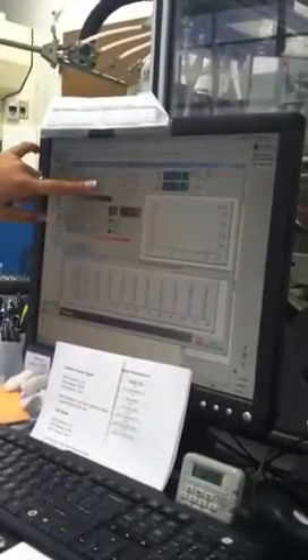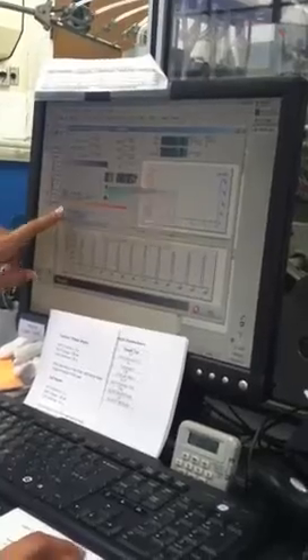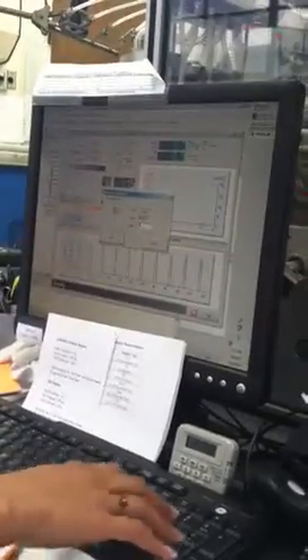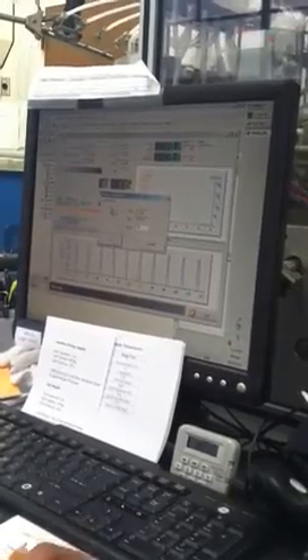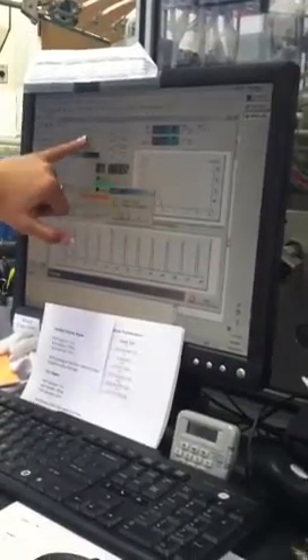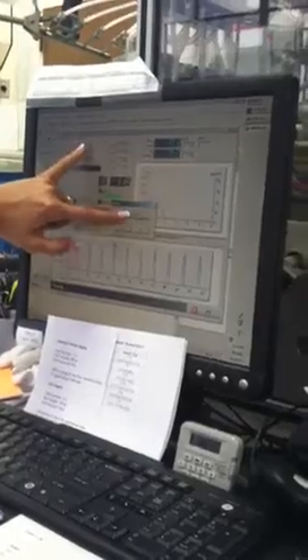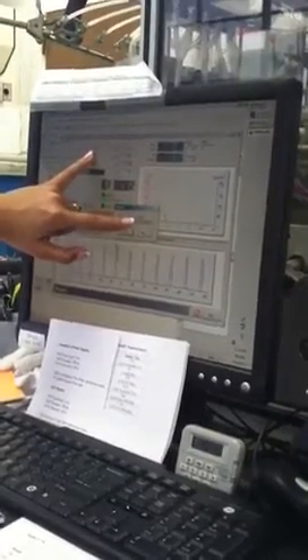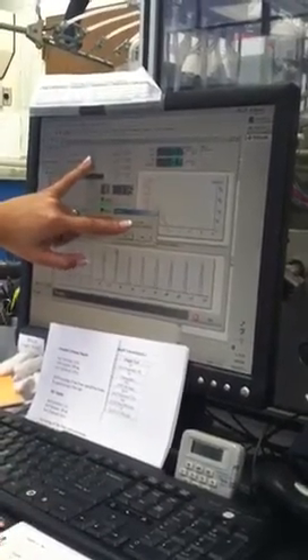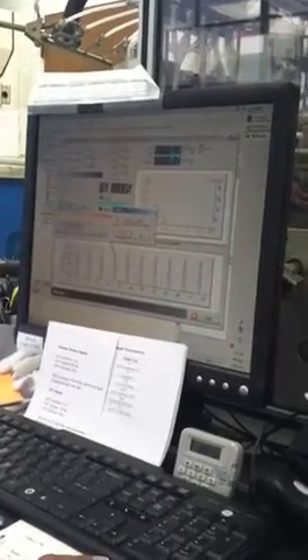Obviously not 35, it's 34.15. So after it's done running, you hit set volume, and it'll ask what your new value is. You enter in what the POF volume should be, 35 mils, and click OK. Now, see these old coefficients? See how it's changed? You'll want to record the new coefficient, just recording it lets you track that you've completed the calibration.